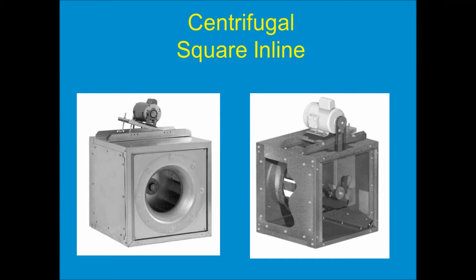We'll take that same centrifugal wheel and mount it in a square housing and it becomes a square centrifugal inline fan. The air is drawn into the center of the wheel — you can see that on the left-hand image — and the right-hand image shows the back of the fan. The air comes off the blades at 90 degrees, pressurizes that square plenum box, and then leaves via the path of least resistance out the back. We use this type of fan quite often in inline applications ducted on both sides — it's a very efficient, very reliable way to move air.